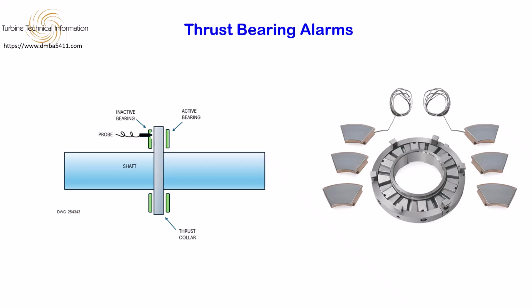A thrust channel is a critical component of machinery protection. Its primary purpose is to ensure the rotating and non-rotating parts don't collide, by monitoring the axial position of the shaft relative to the thrust bearing faces.